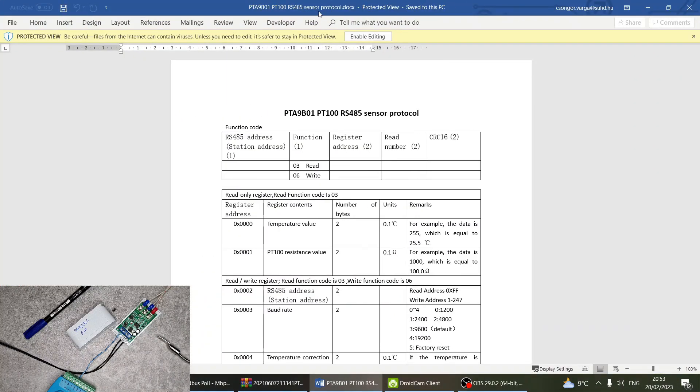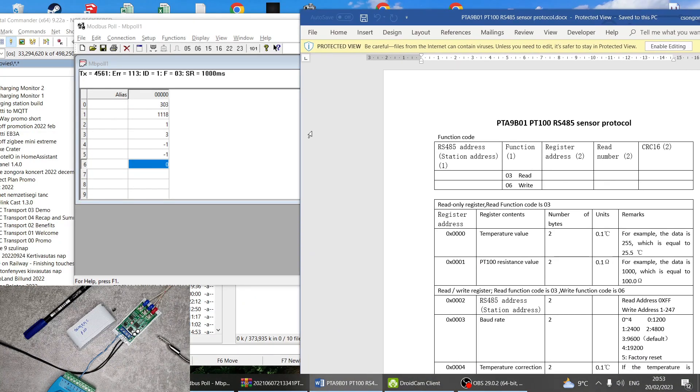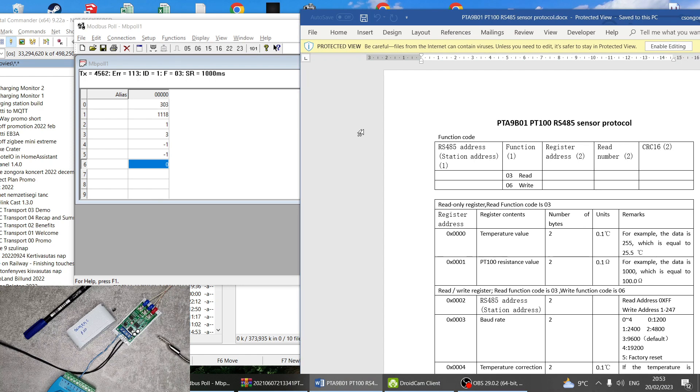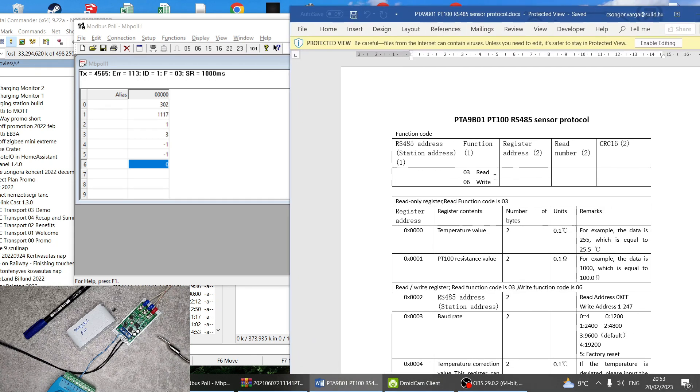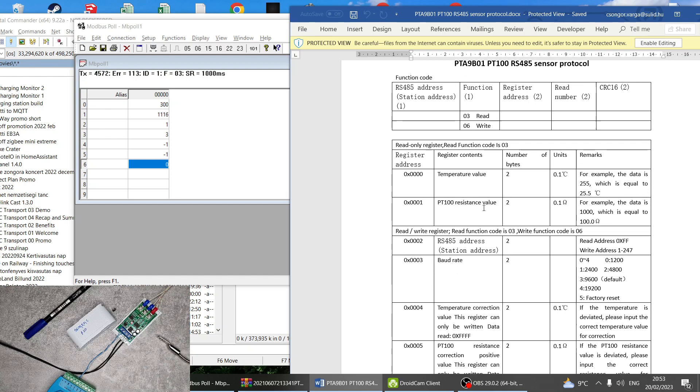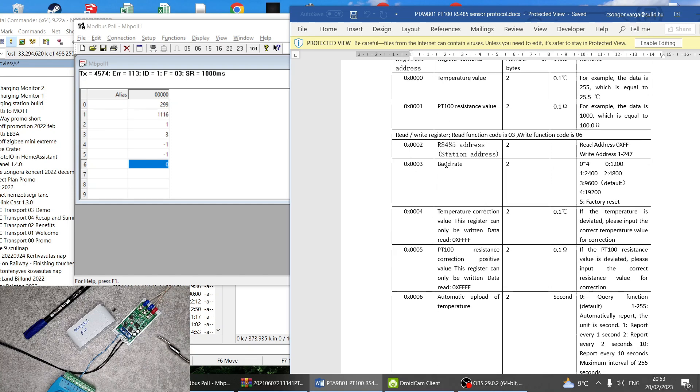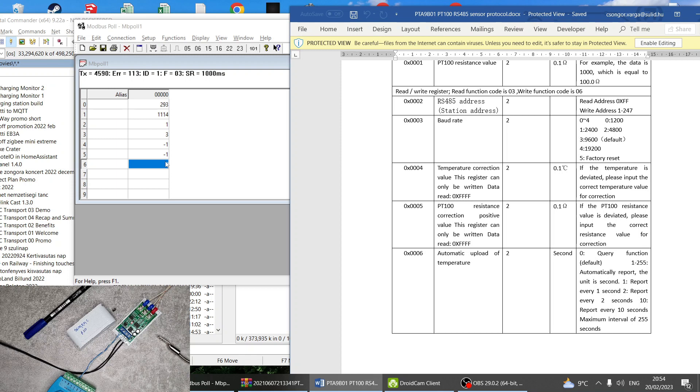So it's all mentioned here. You only use Modbus function 3 and 6, so you either read holding register or write. You can see the temperature value and the resistance value, then the Modbus address, you have the baud rate so you can pre-select from these values here. Then there's this automatic upload which will just send the readings over RS485 all the time, but I think it's just easier to leave it in value 0 or zero mode where you can just use Modbus to read it every so often that you need.